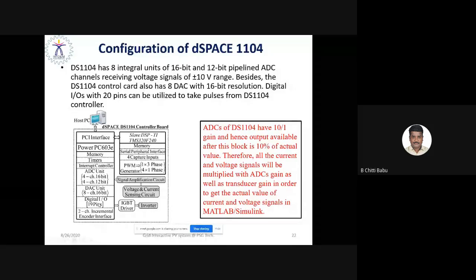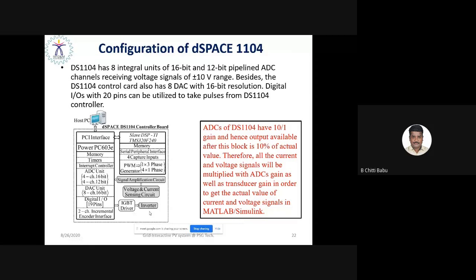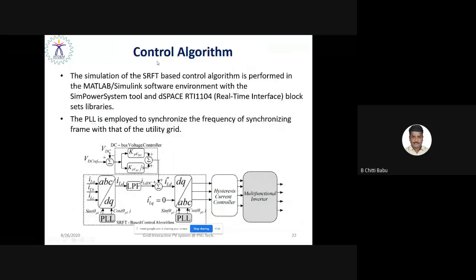So as it generates the digital pulses, that will be given to the IGBT driver circuit, so that it is able to generate the real PWM pulses that will activate the switches in the inverter, so that the inverter is able to implement an algorithm so that it will take an action to control active and reactive power in addition to power quality improvement. And this is the simple control algorithm.